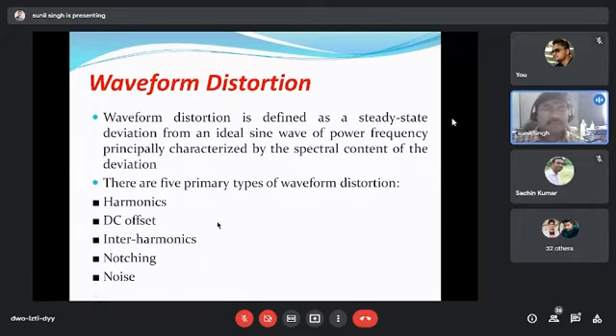Now come to waveform distortion. Waveform distortion is defined as a steady state deviation from an ideal sine wave of power frequency, principally characterized by the spectral content of the deviation. We know that our power has a perfectly sinusoidal waveform. If there is any deviation in that sinusoidal waveform, then it is known as waveform distortion. In waveform distortion, 5 subcategories are there: harmonic, DC offset, interharmonic, notching, and noise. The most important is the harmonic, so in this session we'll take only harmonics.